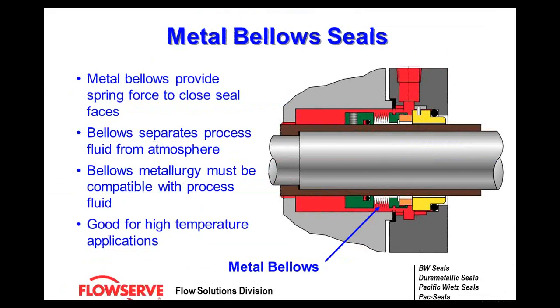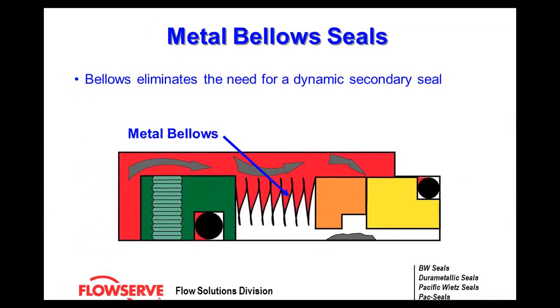A metal bellows provides spring force closure. A metal bellows looks like an accordion — a set of metal rings all welded together. The bellows separates the process fluids from the atmosphere. The bellows metallurgy must be compatible with the pump fluid, and they work excellent in high temperature applications. Because there is no dynamic o-ring, metal bellows are non-pusher seals. If you don't see a dynamic o-ring, you have a non-pusher seal with some sort of bellows, eliminating the need for that secondary gasket.